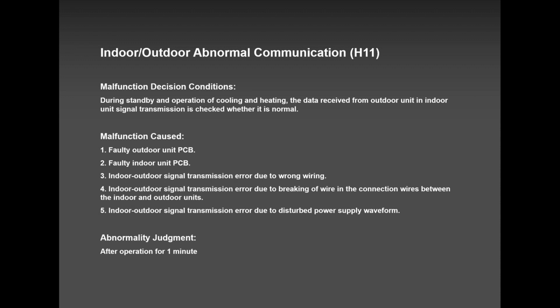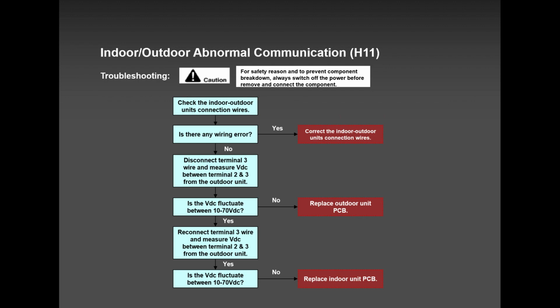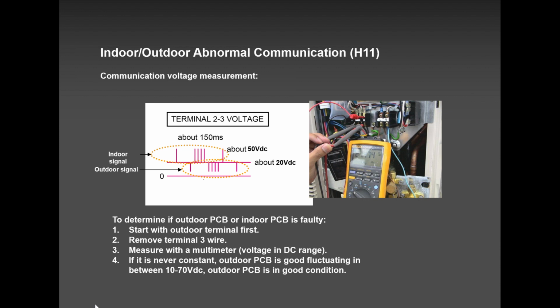Okay guys, H11 on an older installation, most likely 99% is the outdoor PCB, or something has happened with the outdoor board, or with the electronic expansion valve coil. Okay guys, so please, H11 on a brand new install is definitely your wiring mess up. On an old installation, start with the outdoor unit, and it's so easy. The app guides you step by step. All of what you see here is from the app. Disconnect terminal 3 at the outdoor unit and measure between 2 and the screw, and check using this multimeter.